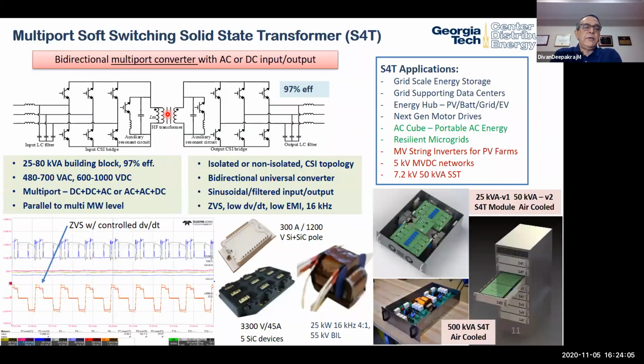We've also been working on a very exciting technology we call a multi-port soft switching solid state transformer, or S4T. This is a power converter, but a very different kind. It's got input and output bridges that look familiar, except inside we have a high frequency transformer, and these devices are all reverse blocking. We've designed it so all devices operate under soft switching conditions.